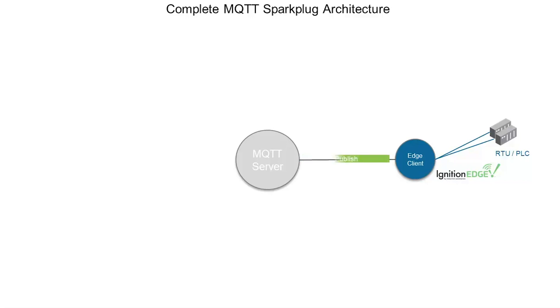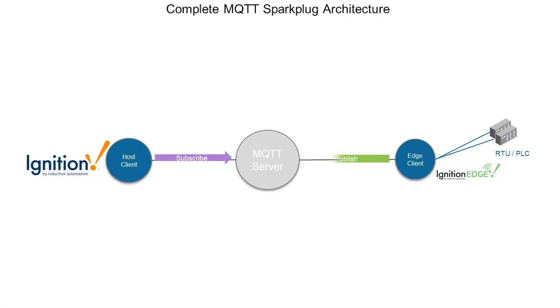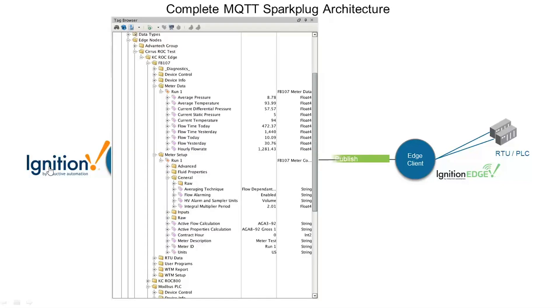This is decoupled — we're publishing that information without really caring who's going to subscribe to it. We'll add another MQTT client running on an Ignition Gateway that can connect and subscribe to Sparkplug information being published by one or more edge devices. As soon as that subscription is issued, we receive those Sparkplug payloads and basically immediately learn our tag tree. Whether it's one edge device or a thousand, your device hierarchy, tag hierarchy, and all of your tags are learned automatically — eliminating months, if not man-years, of tag configuration. When those tags change in the field, they're automatically reflected in a new publish from the edge-of-network devices.